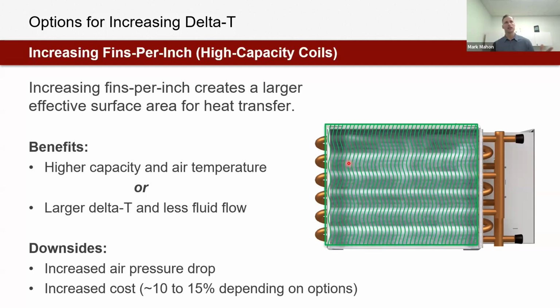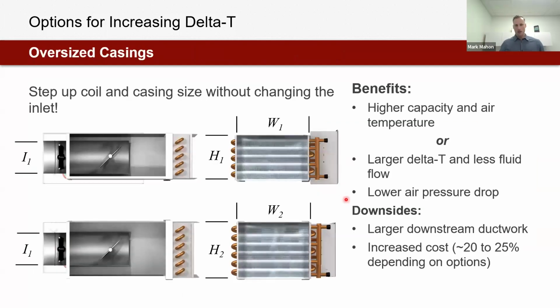Now, this is great because we can get a higher capacity or air temperature, or more importantly, in the scope of this conversation, we can get a larger delta T and less fluid flow. But there is a downside, and that is an increase in air pressure drop. The other option that would be available to us would be oversized casings. And this is the one that I prefer. This is my preference. This is the one that I would lay out if I was the specifying engineer.